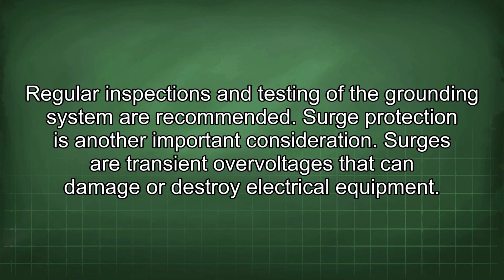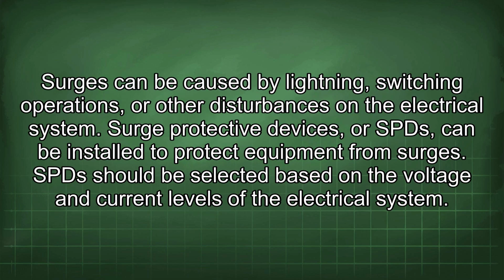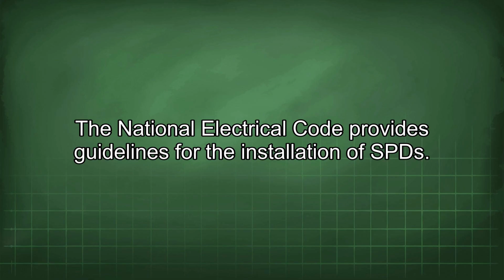Surge protection is another important consideration. Surges are transient overvoltages that can damage or destroy electrical equipment. Surges can be caused by lightning, switching operations, or other disturbances on the electrical system. Surge protective devices, or SPDs, can be installed to protect equipment from surges. SPDs should be selected based on the voltage and current levels of the electrical system. The National Electrical Code provides guidelines for the installation of SPDs.